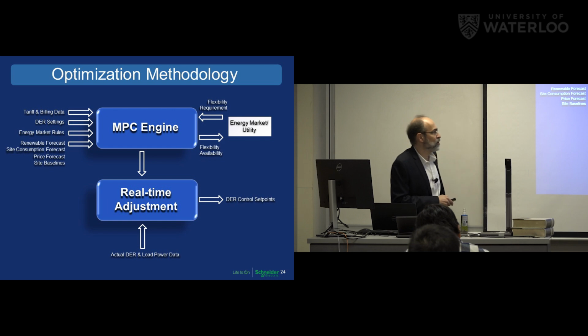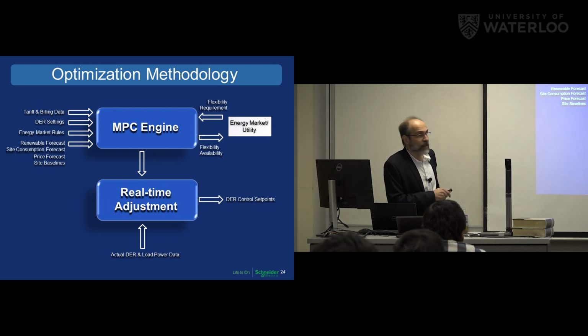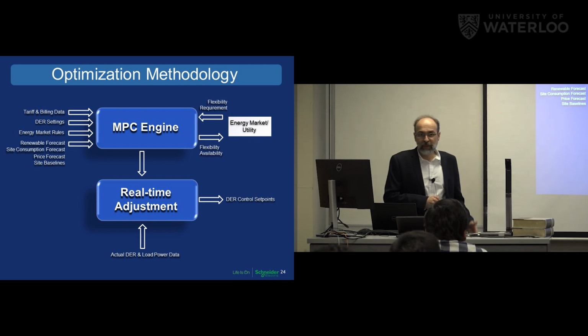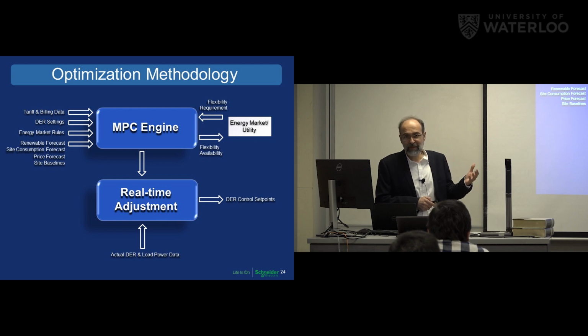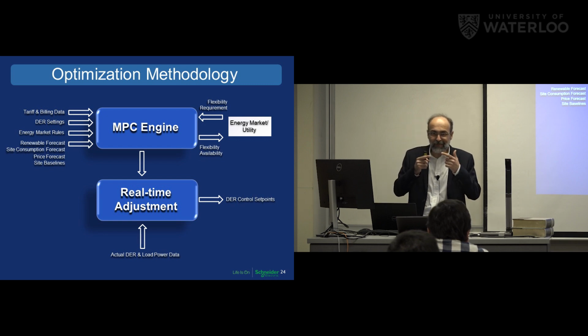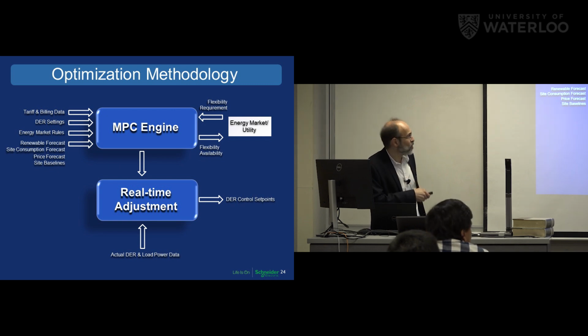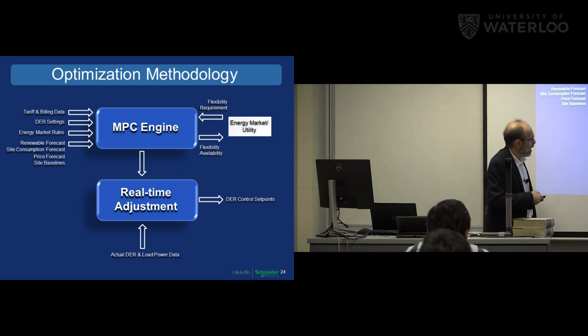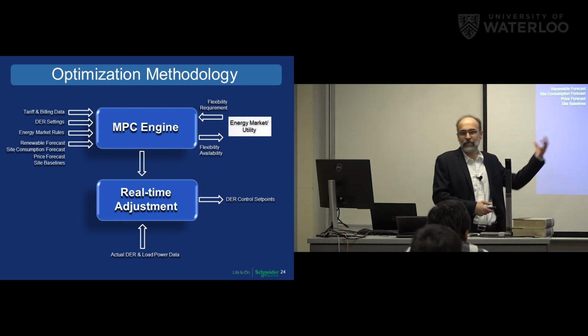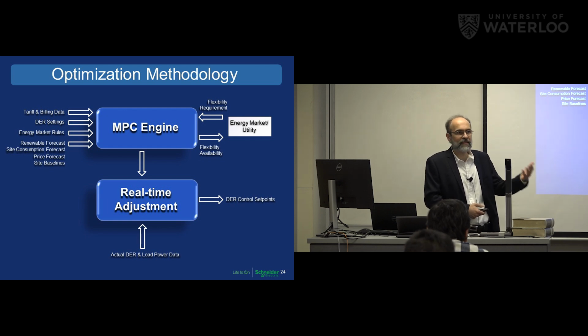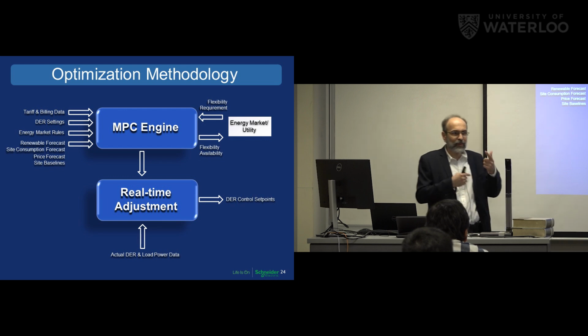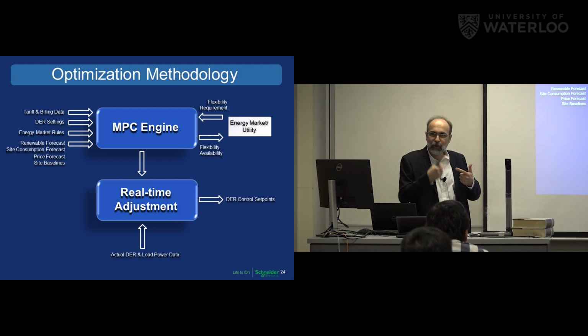We have to have some kind of real-time adjustment, because this system makes decisions every 15 or 30 minutes. But in real time, so many things happen. Maybe all of a sudden one diesel genset or one CHP unit becomes unavailable, or your forecast is inaccurate. So in real time you have to take care of this adjustment between generation and load, to handle that imbalance. That's why we have to have actual DER and load power data ingested into this platform, for example every few seconds or every 10 seconds, so in a very fast loop we can take care of that imbalance.